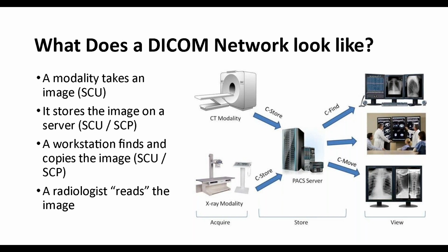It can be a user in the case of a modality like ultrasound that doesn't need to receive an image from anyone. It just transmits, right? It can be a provider like a printer. That's a print server, like those early print servers. Never really sent a file out, but it just received files, right? And then printed to its attached printer. Or it could be like an archive, where I'm going to send it to you. Great, that's a provider role, right? And then I'm going to request, hey, could you send me an image? And then it's going to flip to a user mode and send to me, right?